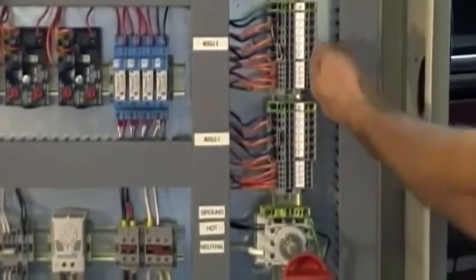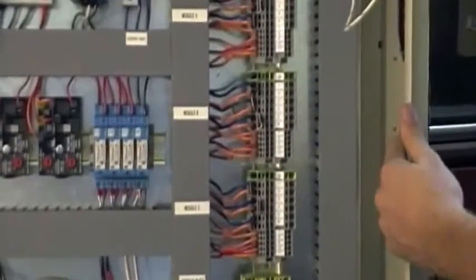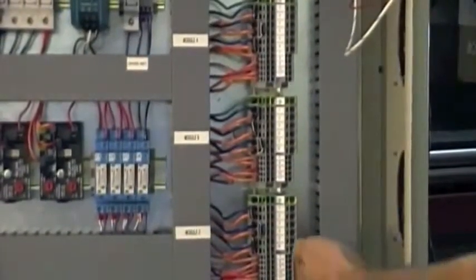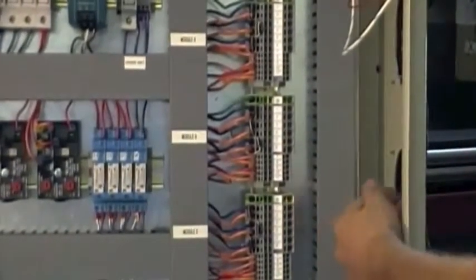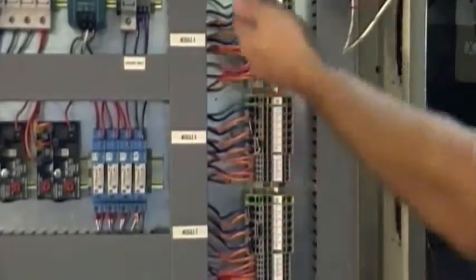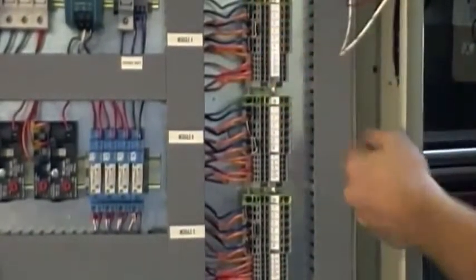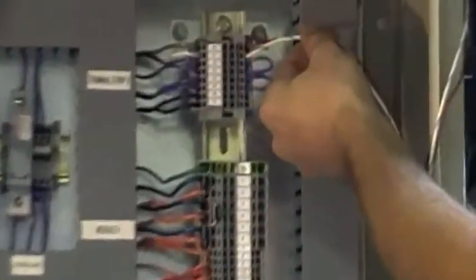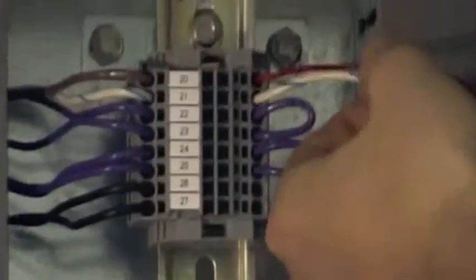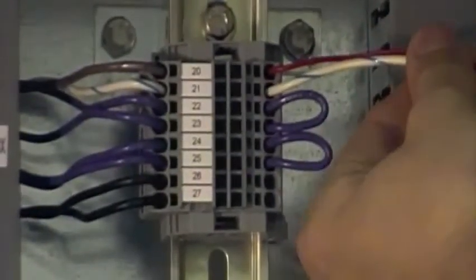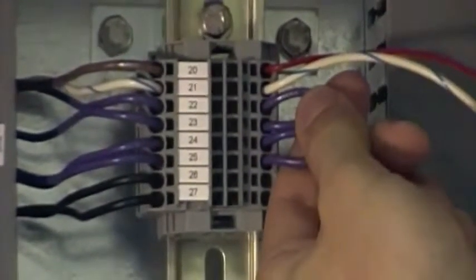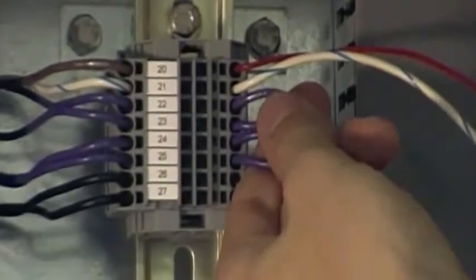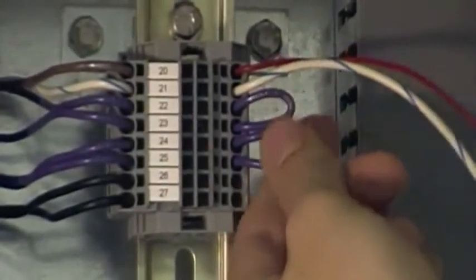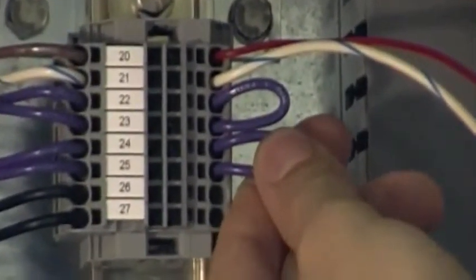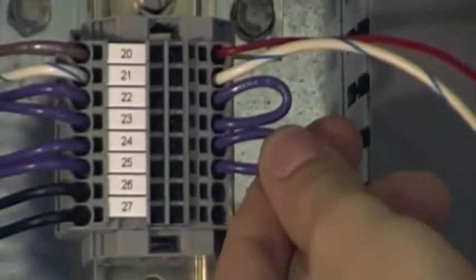These three terminal strips represent the three DT humidifiers, and they'd be wired according to the color diagram included with your prints. The terminal strip X is for your BMS signal and sensors. 20 and 21 are your BMS signal, 20 being your signal hot, 21 being your neutral. 22 and 23 is your airflow switch that is included that you would wire in here. 24 and 25 is your remote shutdown to shut off the system.